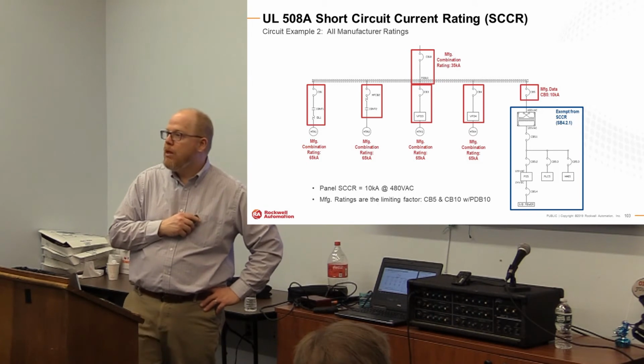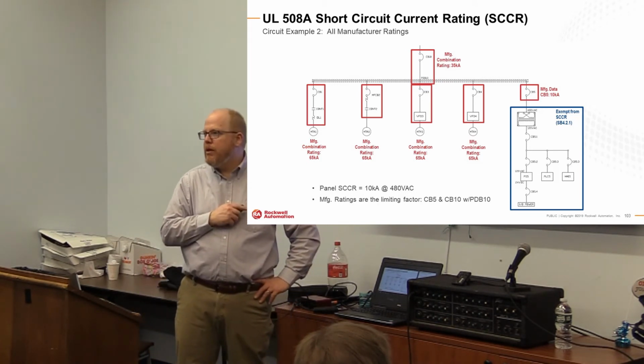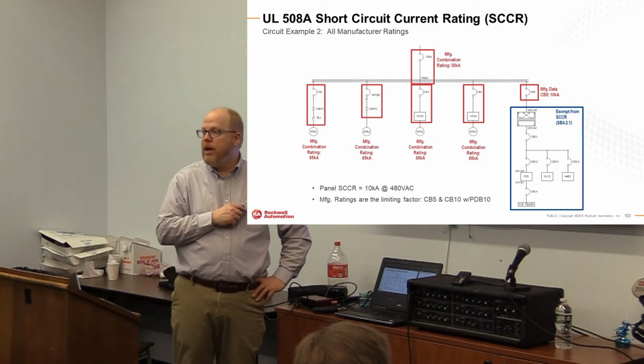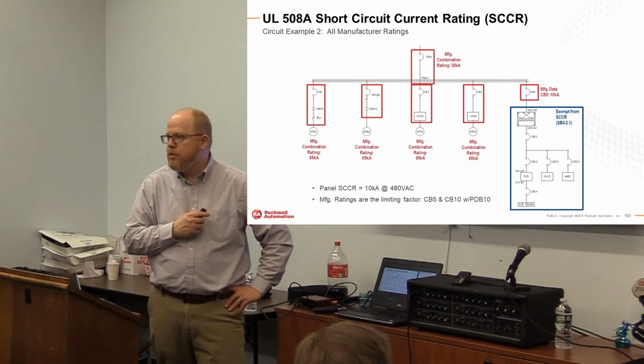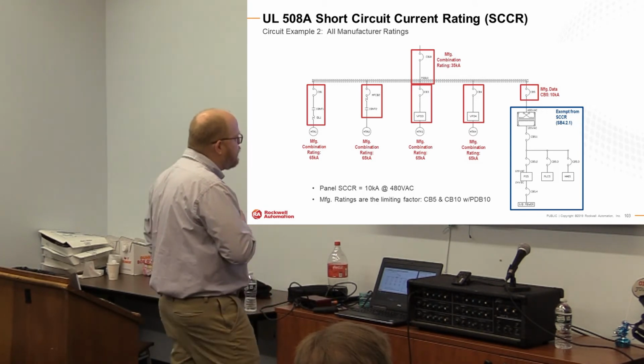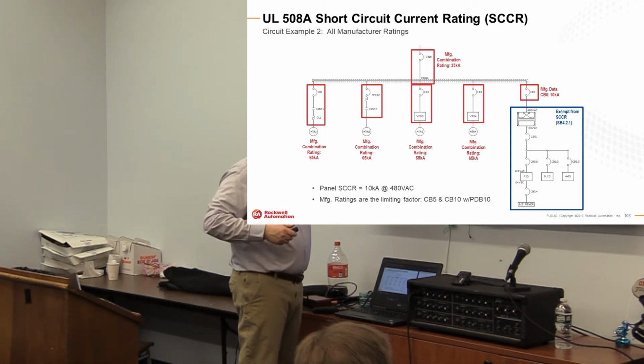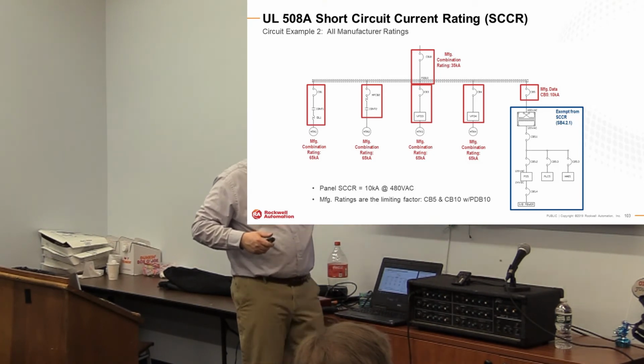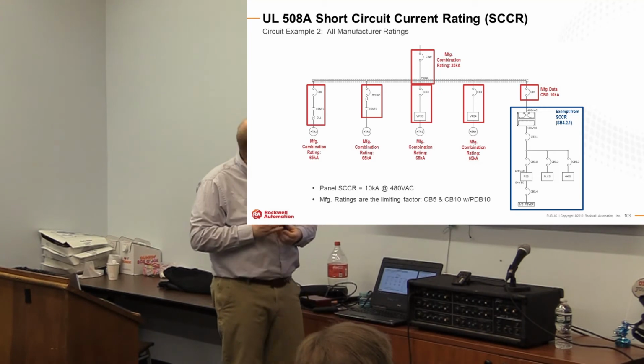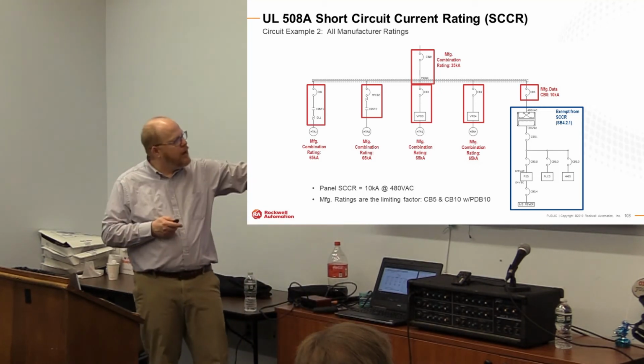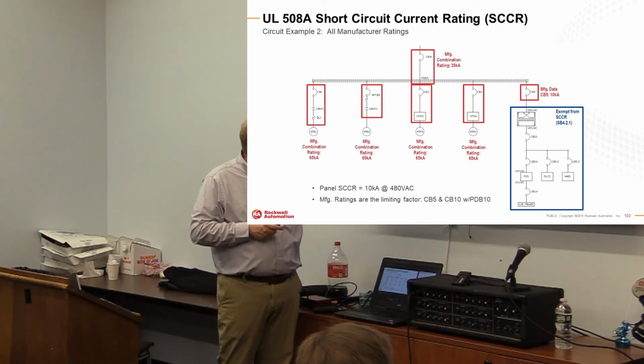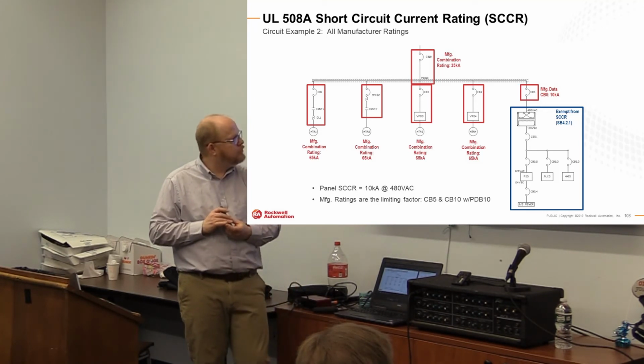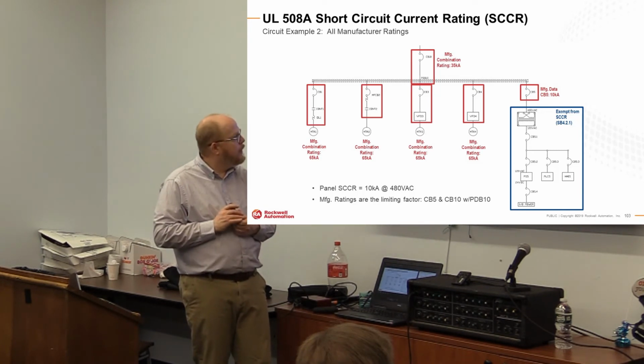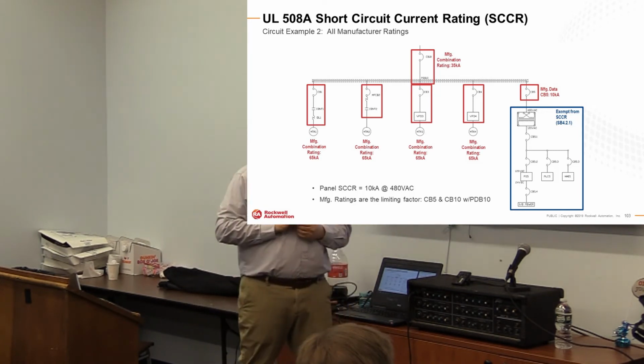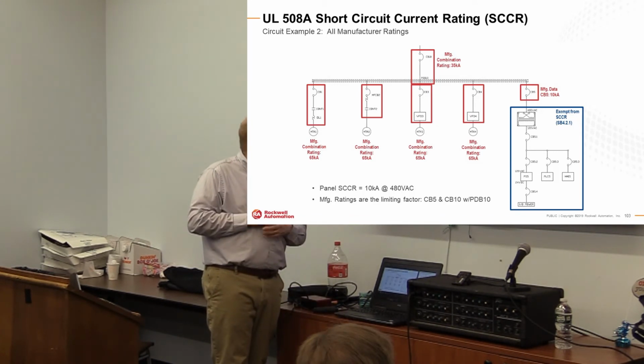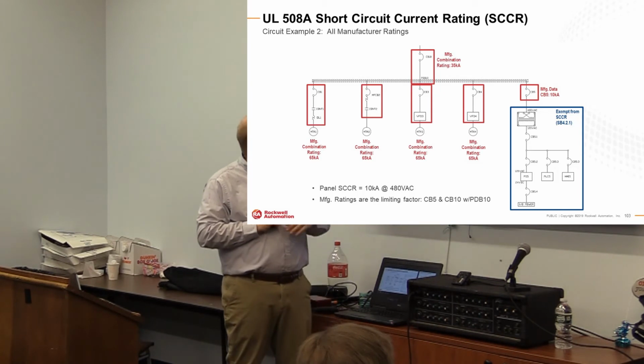And similarly, this is a similar example. The only thing you'll notice here is I went to a fully combination rated power distribution block, on a multi-tap lug type thing. So it carried a combination rating of 35. And you see each of my branches were 35, but this breaker over here, I'm still cheaping out using a little mini breaker, and that's 10. That fella right there would be our limiting factor. And so we would want to go with 10, or we want to swap him out. If we wanted to go with 35, we could put something different in there. But 35 would be the most we could ever get because of this manufacturing.